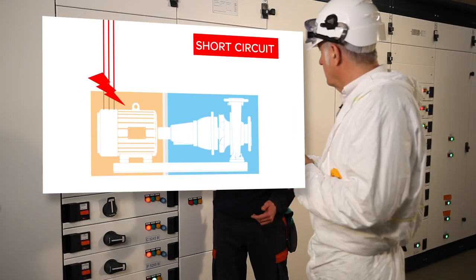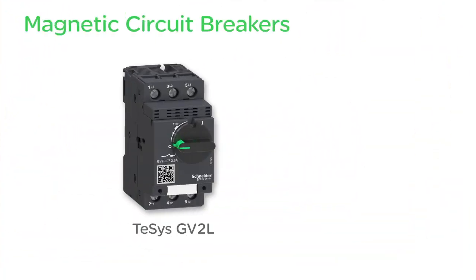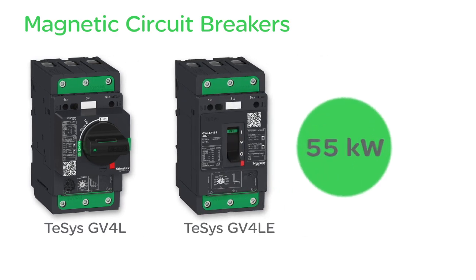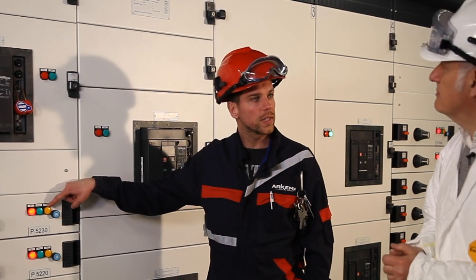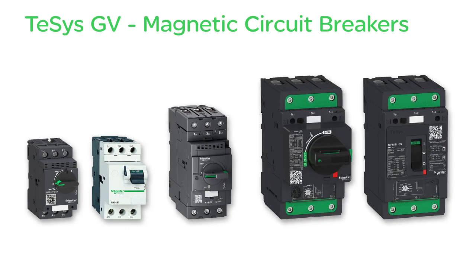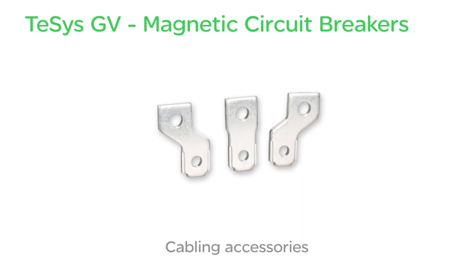You mentioned these risks — if we take a motor, how do we deal with each individually? For short-circuit protection, a magnetic circuit breaker is installed, which protects by disconnecting the power supply. The TeSys GV2 and GV2LE circuit breakers cover power ratings up to 15 kilowatts, GV3L up to 45 kilowatts, GV4L and GV4LE up to 55 kilowatts. It is also equipped with a contact that allows the fault status to be displayed on the front panel and in the control room. The TeSys GV2 circuit breakers can be equipped with accessories such as auxiliary contacts, trip units, wiring accessories, and a remote handle.